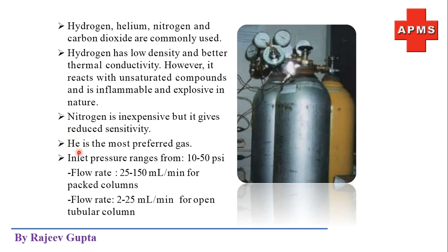Okay, so it does not react with the sample or other parts of the instrument, and it also has high thermal conductivity and low density, so it is the best gas. But helium is very costly, very expensive, so its use is limited. Inlet pressure ranges from 10 to 50 psi, and the flow rates are shown. These normal ranges of carrier gas flow are shown.